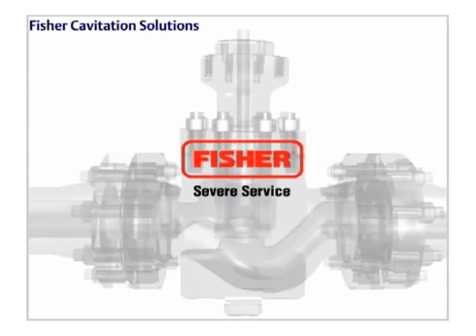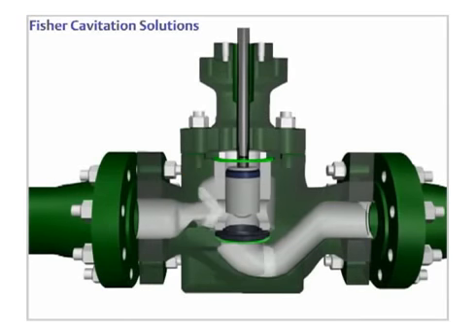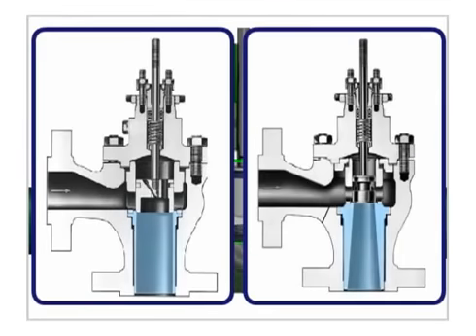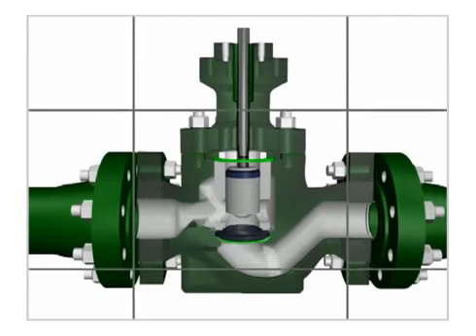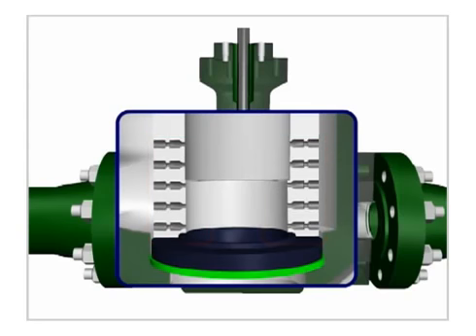Cavitation damage can often be reduced or prevented by using the proper components. Emerson offers these solutions. Valve liners are constructed of hardened materials to protect the valve body. Pressure staging keeps the pressure from falling to near a liquid's vapor pressure, which helps prevent vapor bubbles from forming.